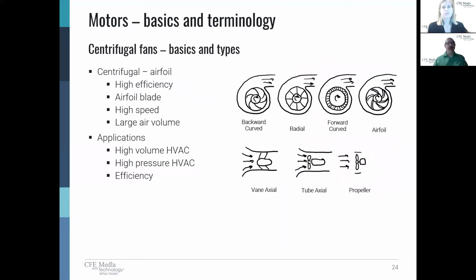If I really want to get the most out of a centrifugal fan, I'm going to go airfoil backward curved. Now, why is that? Well, I'm just simply changing the blade design to be as good as I possibly can. Now we can hit efficiencies better than 80%. I also have the highest pressure and the highest volume of air that I could possibly move and the highest efficiency. It's great. Why wouldn't we use it all the time? Well, it also obviously comes with an increase in cost.